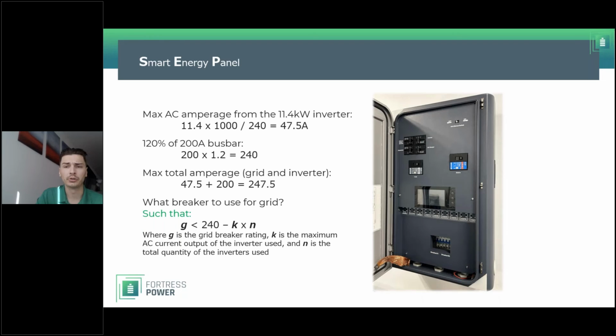What breaker do you want to use for the grid? Up in the top right hand corner, you want to use a grid breaker rating that is less than 240 minus the output of the inverter used, multiplied by the total quantity of those inverters used.